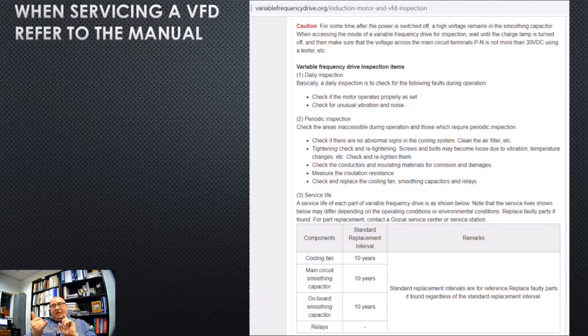safety-wise, that the DC bus is not holding a charge, that you allowed enough time for it to dissipate. You check it with your meter, both on AC and DC. Don't block the air vent on a drive with a piece of paper. And also know that just because the drive is not running doesn't mean that it's powered off. You got to remember you have two sources of power that's going to activate the drive.